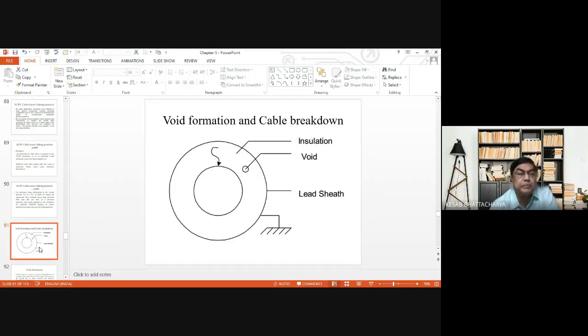Now, cable breakdown. Here it has been found that, if we consider for simplicity a single core cable, over the conductor a number of layers of insulating materials will be there. These cables often undergo different types of load cycles. Sometimes the load will be much more in the cable, say during a particular time of the day when the load is maximum. A maximum current is flowing through the core, and obviously when the current is maximum, the heat developed inside the core will also be maximum.